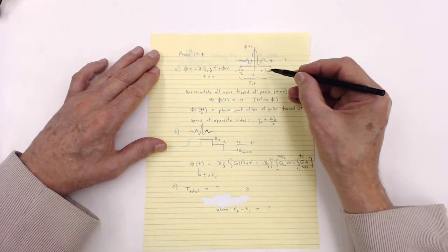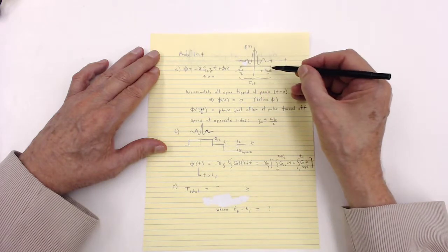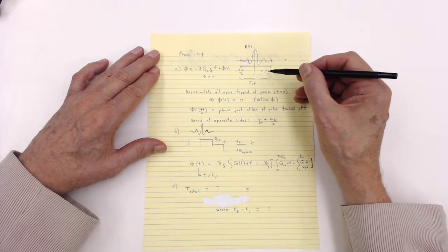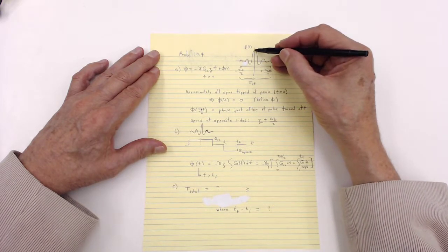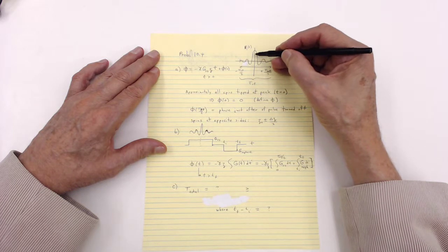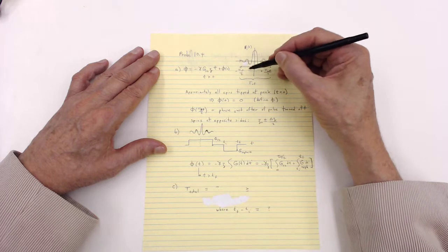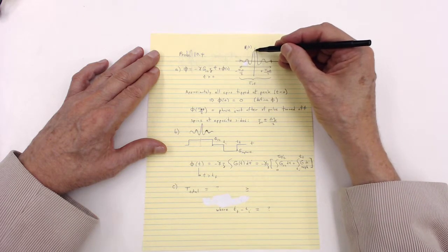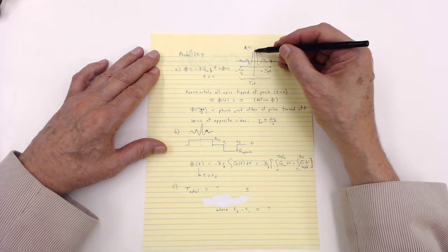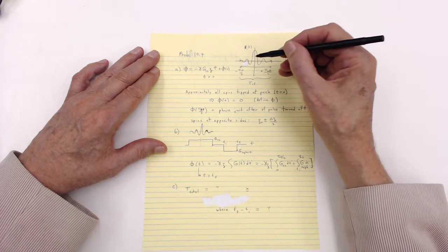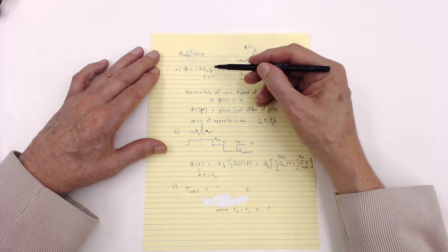Now, in contrast to the previous problem, I'm going to call tau RF the total time that this pulse has been on. And now, I'm also going to assume that all the spins are, for the most part, tipped right at t equals 0 with the big peak here. So before this, no magnetization in the transverse plane. Now I've got magnetization in the transverse plane, maybe still some in the longitudinal, but I've got something in the transverse plane, and it starts to precess in the rotating reference frame because I've got a gradient on. I've got the slice select gradient.